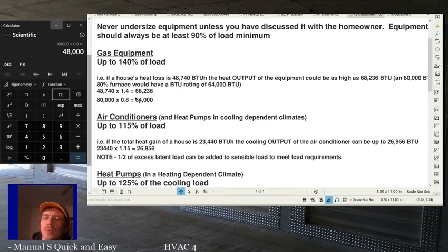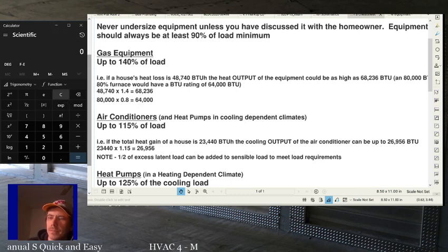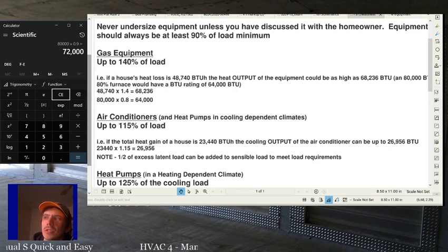48,740 times 1.4 equals 68,236. 80,000 times 0.8, and that's assuming an 80% furnace, would be 64,000 BTUs. If it was a 90% furnace, that would be 80,000 times 0.9, which would be 72,000 BTUs. So a 90% furnace in this case would actually be too big, right?